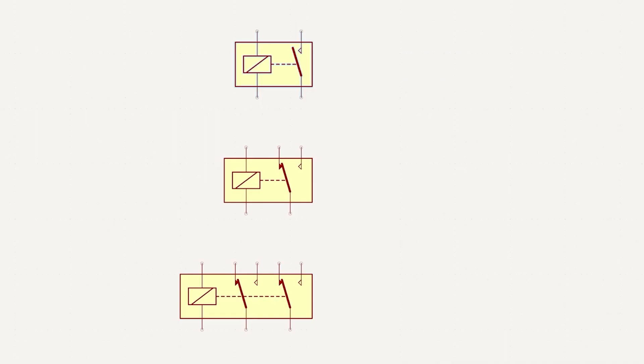The armature will usually be composed of a ferrous material that is attracted to magnets, though sometimes the armature is non-magnetic, and in that case we'll have a ferrous slug welded to it. In the relay's unenergized state, there's a spring that holds the armature to the normally closed or NC side of the circuit. The electrical device that actuates the armature into contact with the normally open or NO contact is the electromagnet.